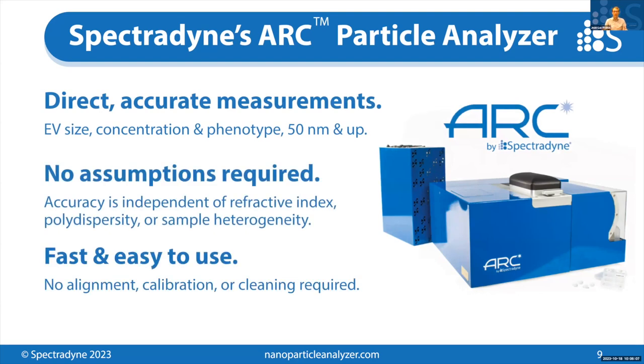This is Spectradyne's second product, the ARC Particle Analyzer. It delivers direct and accurate measurements of EV size, concentration, and fluorescence-based phenotype, starting at around 50 nanometers and up. Importantly, this technology requires no assumptions about your sample — its accuracy is independent of refractive index, the sample's polydispersity, or the heterogeneity of the sample in terms of size or other physical properties. Finally, it's fast and easy to use: there's no alignment, calibration, or cleaning required in order to operate this instrument regularly.